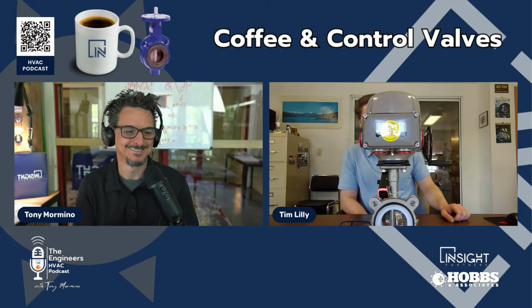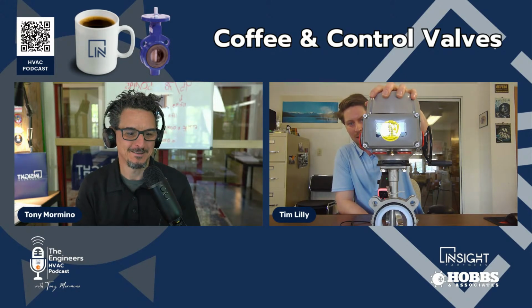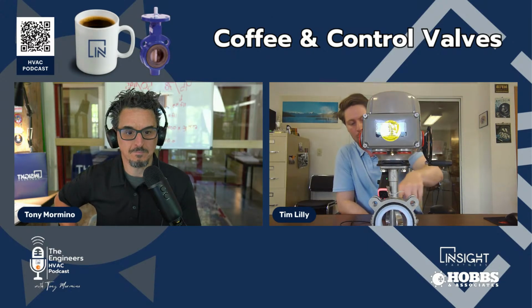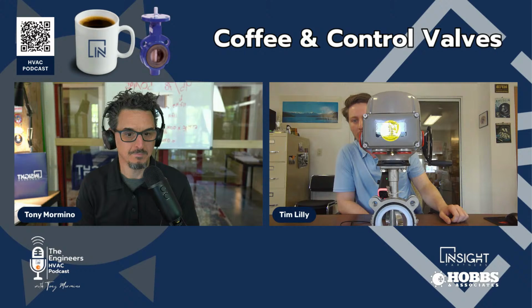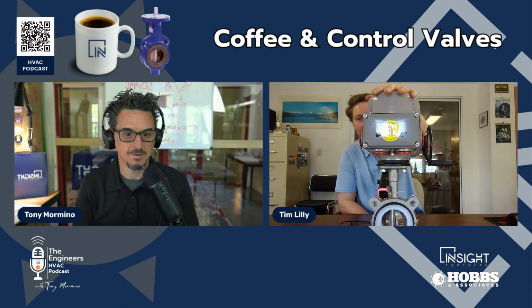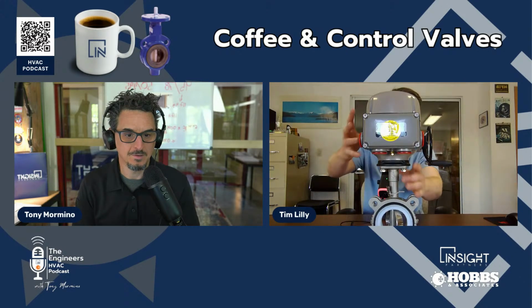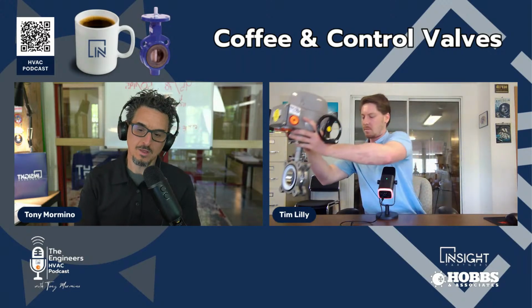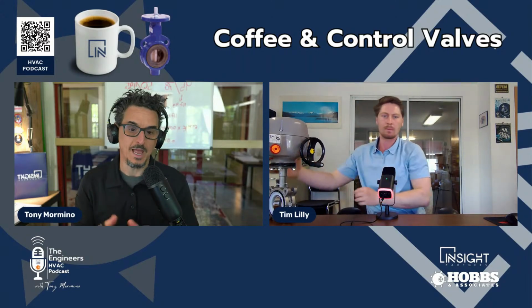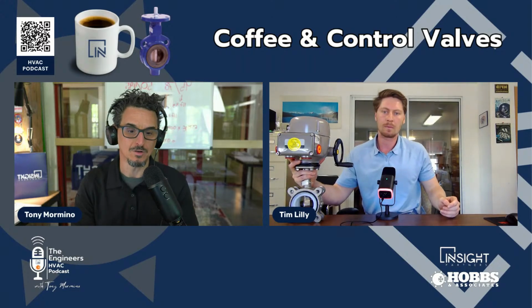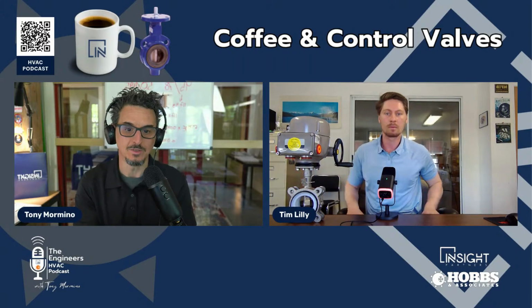So it's great. Right. And then this is an electric actuator. And so it's very simple. You just run a wire or two to this, and then you give it a signal on a 0 to 10 scale, and then it'll move your disc and it'll modulate your flow. It'll go open, it'll go closed, and you can sit in your control room and set your program, send your signal. You can run an entire steel mill with 2 wires, which is incredible. Right. Whoever figured that out is incredible. And you can do the same thing in the HVAC world. And they do it in the HVAC world. So every valve or control valve has an actuator on it or some kind of way to turn the valve or control it, right? Call it an actuator typically. Looks like it's got a built-in feature.